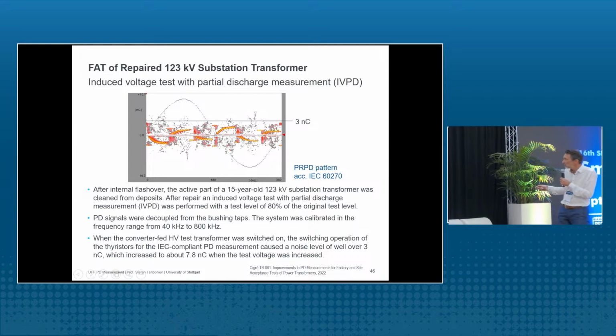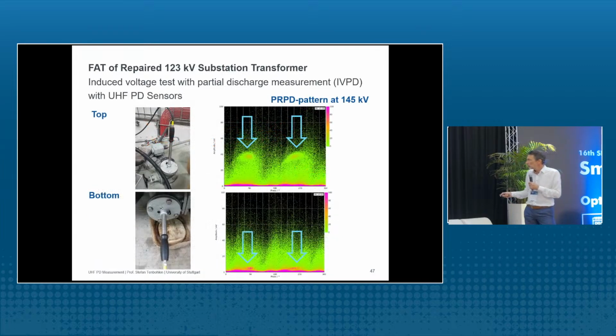Yeah, you can see these thyristor switching here with these, let's say, call it fingers. So you have here a noise level of 3 nanocoulomb, which is very high. Yeah? And due to this high noise level, you could not measure the internal PD of the transformer with an electrical system. So we installed here 2 UHF sensors on the transformer tank, and with the UHF sensors we could measure here internal PD on this transformer.